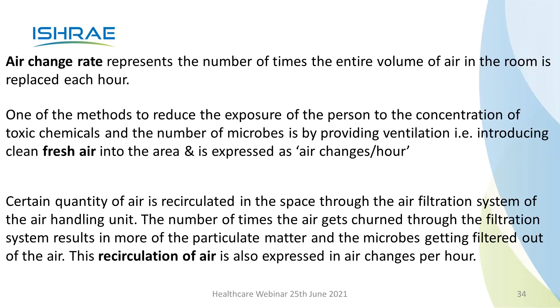A certain quantity of air is recirculated in the space through the air filtration system of the air handling unit. The number of times the air gets churned through the filtration system results in more of the particulate matter and microbes getting filtered out. So one is toxic agents, which only fresh air can help you with, because if those toxic agents are gases, a filter is not going to help you. It's only the fresh air. And the other is particulates, whether pathogens or other particles, which can be taken care of only by the filtration system. More number of air changes, better is the filtration.